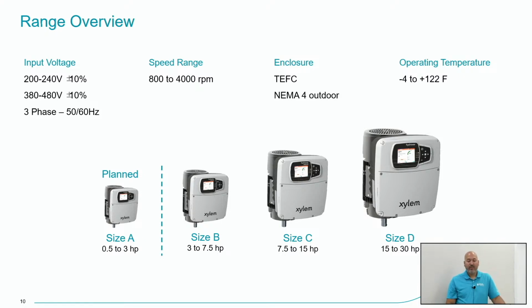On the left there, we have a planned size A. That's a 1/2 horsepower to 3 horsepower product. We do have an offering in that space today, a permanent magnet motor with an integrated VFD. The idea is to refresh that product and bring the technology up to speed with the Hydrovar X, so that we'll have a single offering ranging from 1/2 horsepower to 30 horsepower.